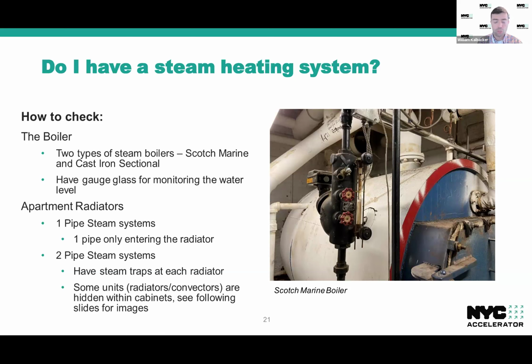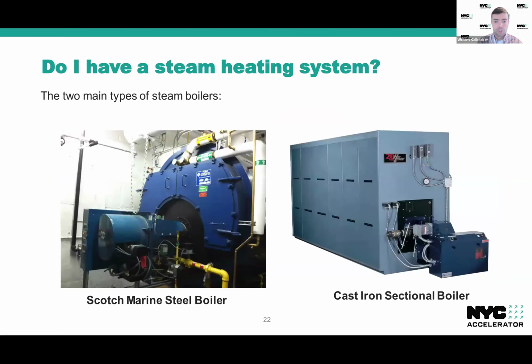On the distribution side, the terminal units in the apartments themselves can also give you an indication if there's steam in the building. There's a couple different species of steam systems, one pipe and two pipe. With one pipe steam systems, you have one pipe going into the radiator. The steam goes in there and comes back out as condensate. And with two pipe systems, just as it sounds, you have one pipe going into the radiator and a completely separate pipe coming out of the radiator. So you can tell that way. Just some visual aids here to help assist in identifying what a Scotch marine boiler looks like on the left and a sectional boiler on the right.